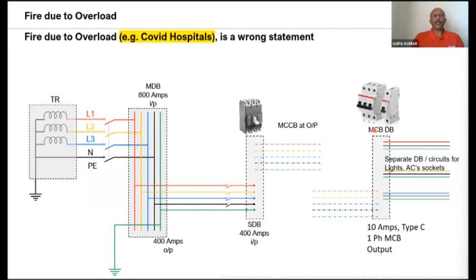One of the fundamental principles adopted in electrical fire, or fire due to short circuit, is that any electrical apparatus which is consuming power of less than 15 watts is not supposed to ignite fire. Or if any fault is reduced to less than 15 watts within 3 seconds, the electrical installation cannot ignite fire. So with this principle, it is very simple to conclude that if this MCB trips within 3 seconds, the problem has gone. There is no fire in that particular installation.